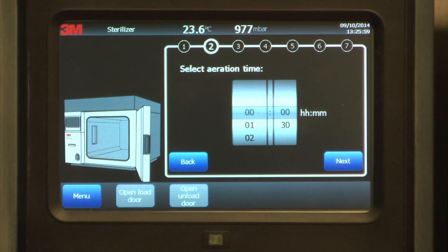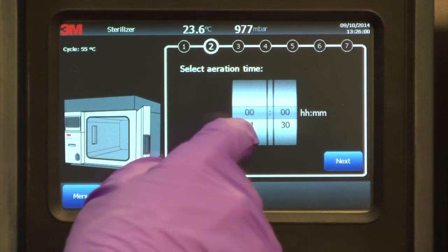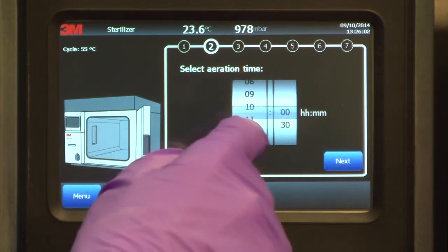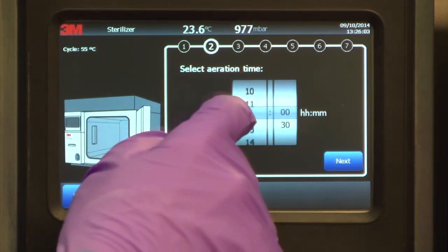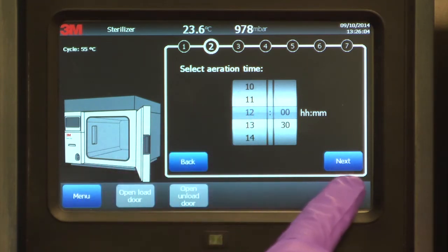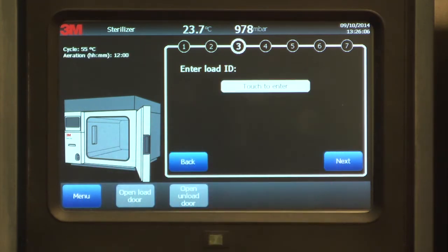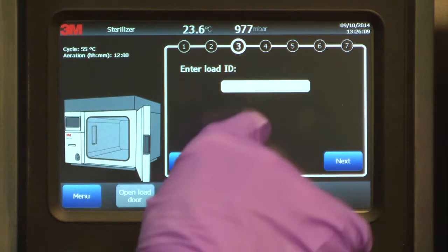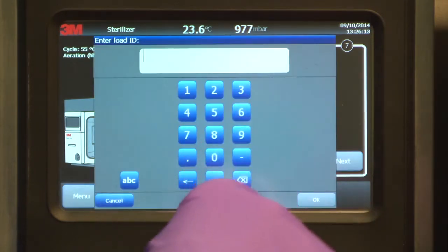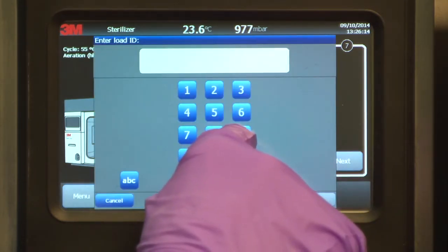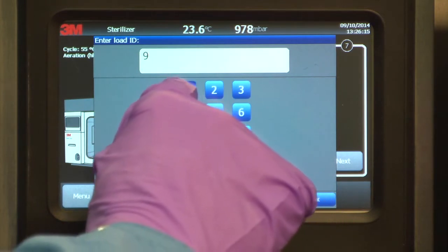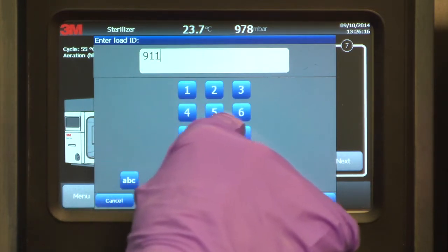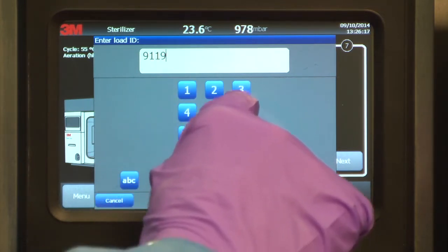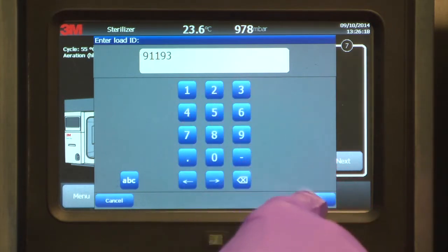Step 2. Select the appropriate aeration time from the sterilizer touchscreen. Aeration removes ethylene oxide residuals from the product load and the devices. Determine the aeration time by referring to the device manufacturer's IFU. Step 3 is an optional step to create a load ID. When you touch the Load ID field on the touchscreen, an alphanumeric pad appears on the screen to enable you to enter a load ID.